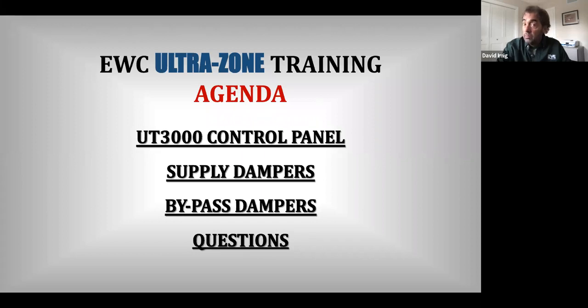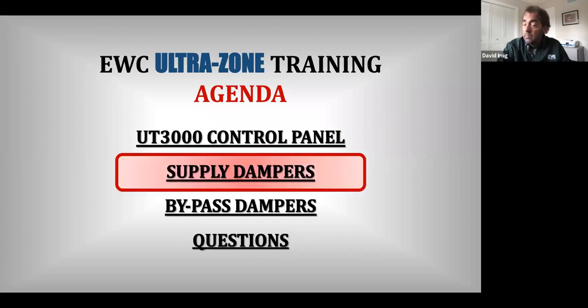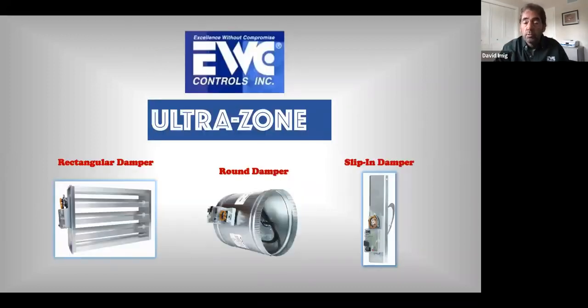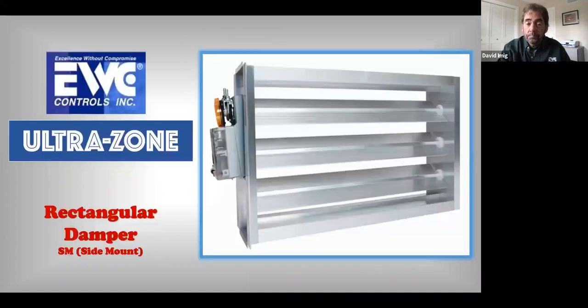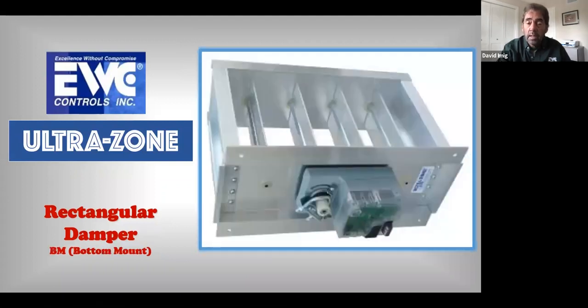That's our UT-3000 panel. Now we look at supply dampers, and quickly a broad overview on these. These are the dampers you use with this product. It is the same exact damper you use for your non-communicating zone systems as well. And that's one of the beautiful things about that. You're not looking at a high-end communicating motor actuator specific damper to use with this product. We have these dampers available in rectangular, side mount, and bottom mount. These dampers come from 8x6 up to 30x30, all even sizes.